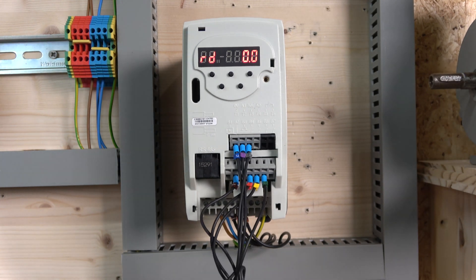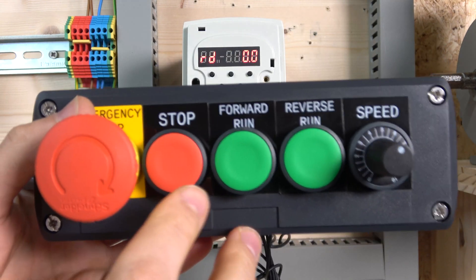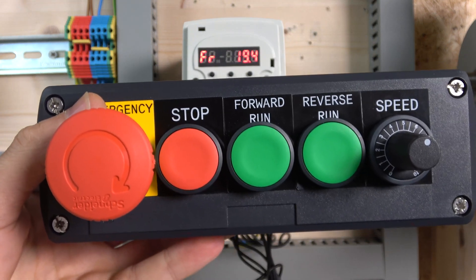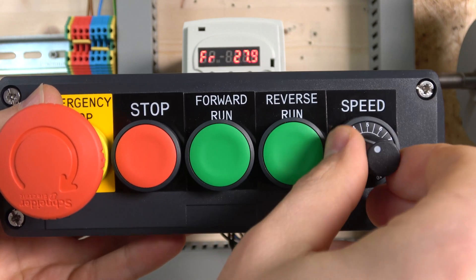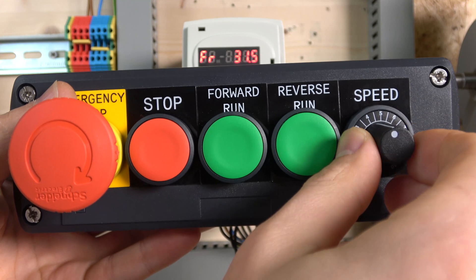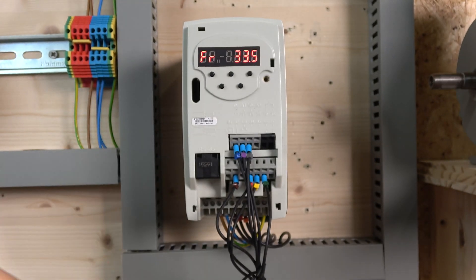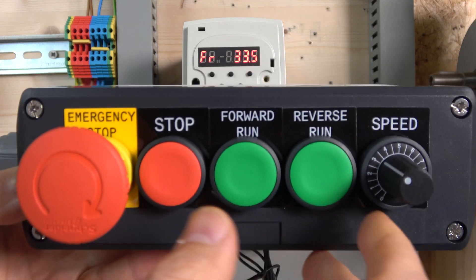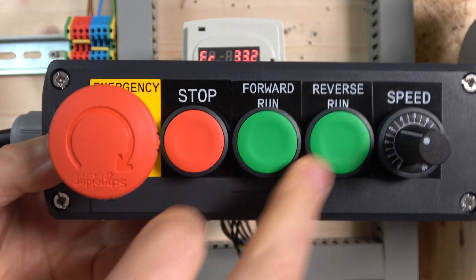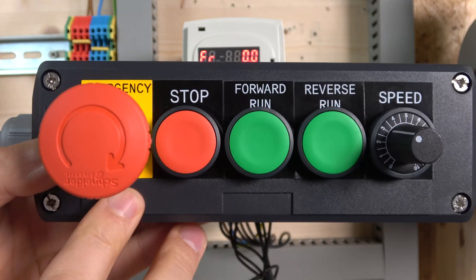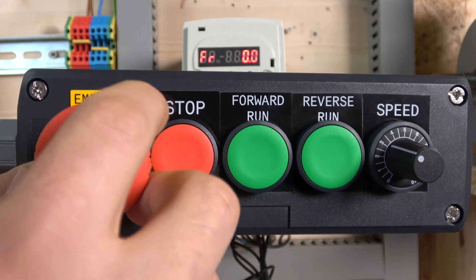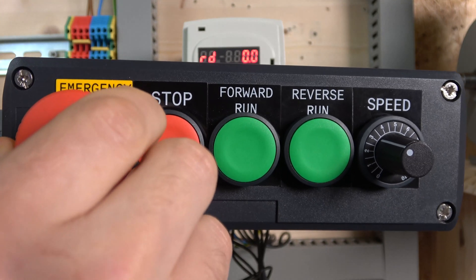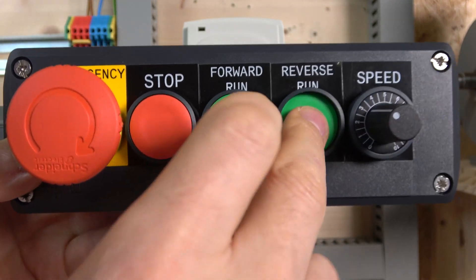Here we are, the station is on. Here we go, quite straightforward. Click the start, it will go forwards. And it looks like my potentiometer is going the opposite way. So if you ever have that problem, just swap the 0 and 10, swap places, and you should be good to go. But nevertheless, we can still test things. You can go straight into the minus, into the plus. And then you got your nice stop in there. And if you ever release that, it has removed enable signals.